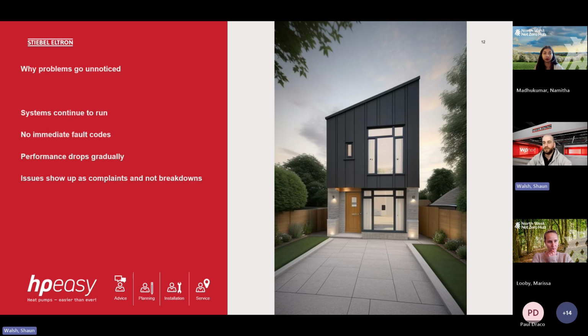What you're more likely to get from tenants or the homeowner is that they'll say the hot water's not quite getting hot enough anymore, or the heating system's not as hot as it used to be. But all of those things generally come back to system settings, sensor placements, water quality and things like that, and the performance will drop gradually over time. But if we service it every year, that no longer becomes an issue.